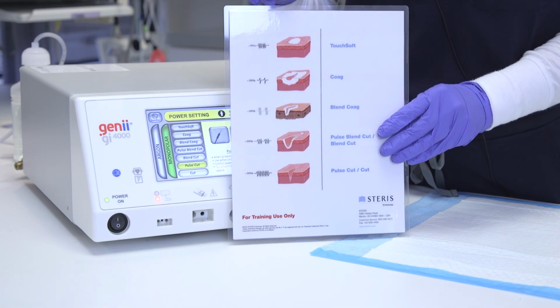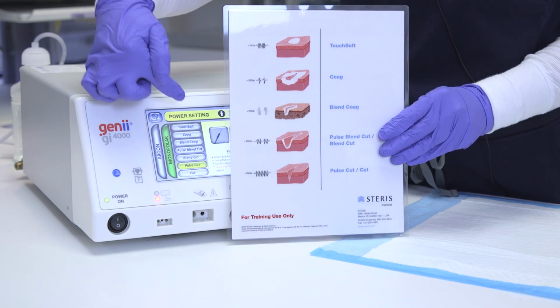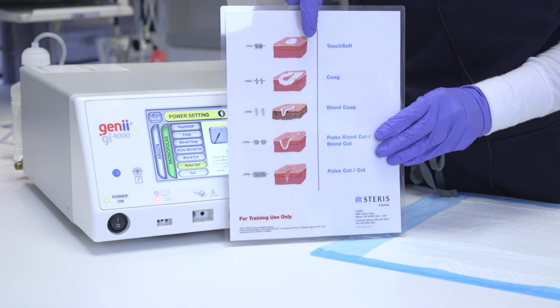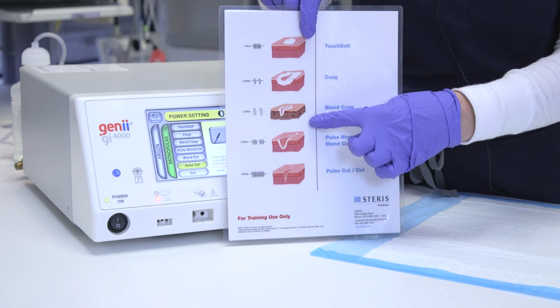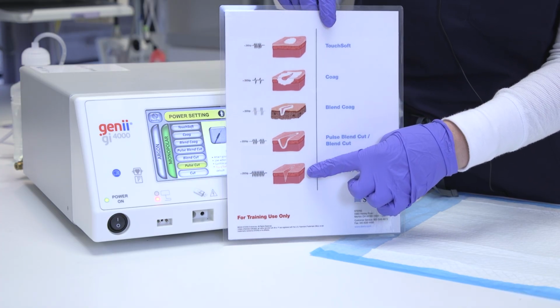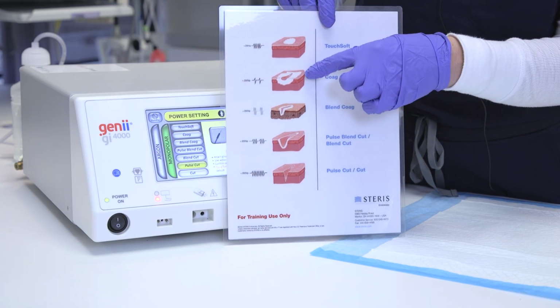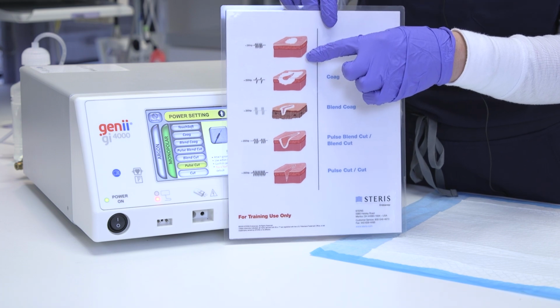The tissue blocks here are a good visual representation of the 7 different modes. You'll notice in touch soft that it's more coagulation, and as you tap down in different outputs, you're blending in more cut. As you tap up, you're blending in more coagulation or hemostasis.